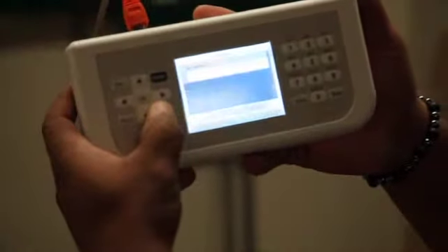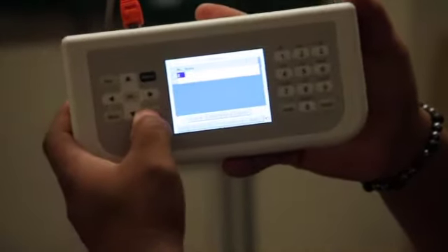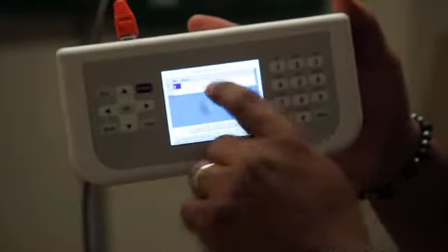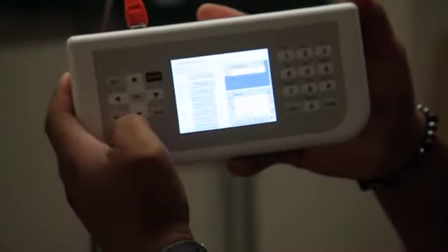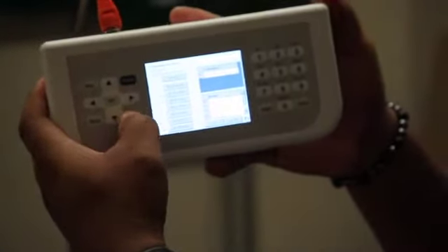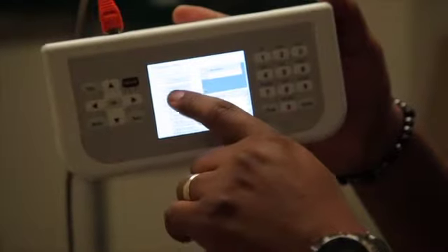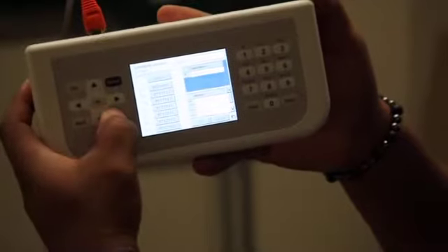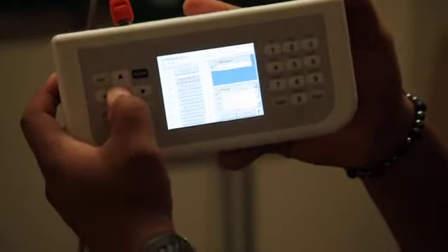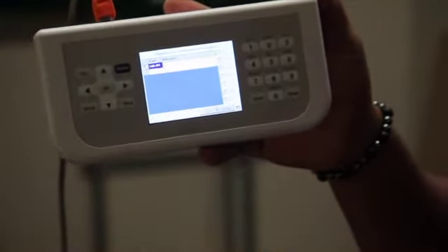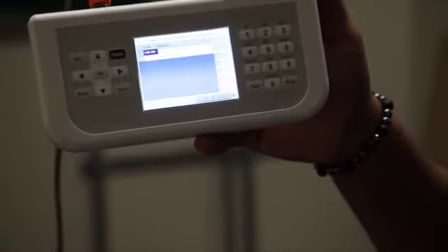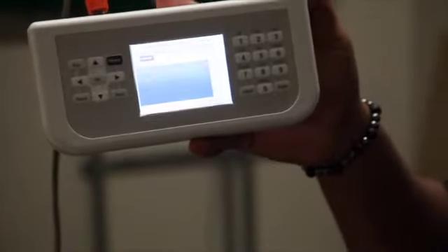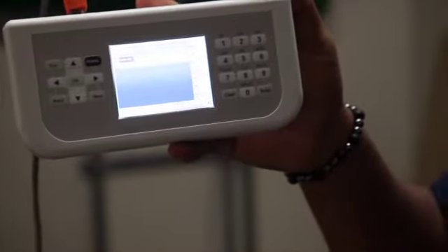So if I go into my corridor schedule by hitting my next button, it highlights that line. I select OK, and it pulls up my schedule details. As you can see here, I have every day of the week selected, which tells me that this schedule is going to run every day. If I hit next to highlight Monday and select OK, it allows me to look at the agenda for the schedule. Basically, you only have one instance here, and that is to enable your schedule to run off of the photocell, occupancy sensor, and digital switch.